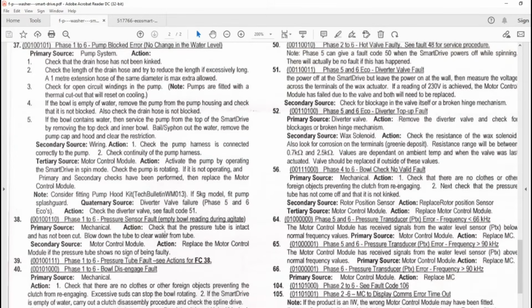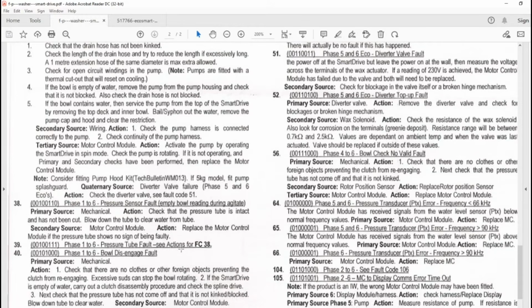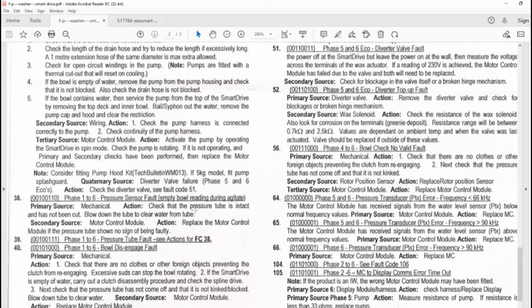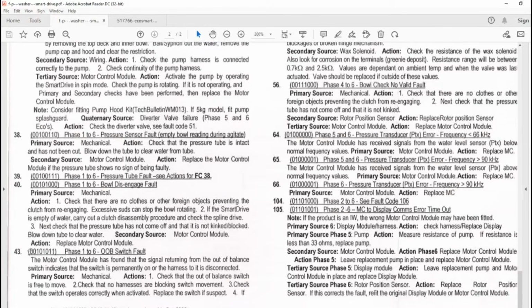Pressure sensor error, pressure tube fault. Now, it could be that you've got a pressure tube being damaged, it's got a hole in it or a blockage, or got water in the tube. If you replace the control board, you've got to take the pressure sensor tube off. You don't want to just plug it back on again. You've got to blow down, make sure there's no water in the bottom of the bowl, drain all the water out so there's no water in the water level sensing system. Otherwise, if it is a faulty sensor, you've got to replace the control board because it's part of it.